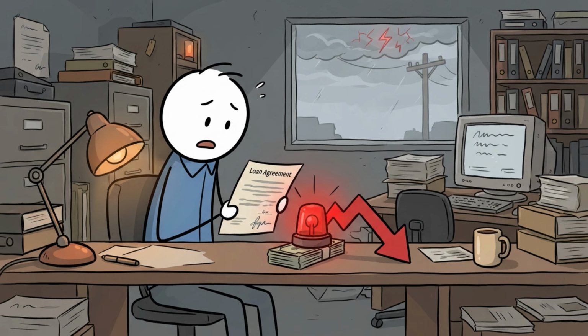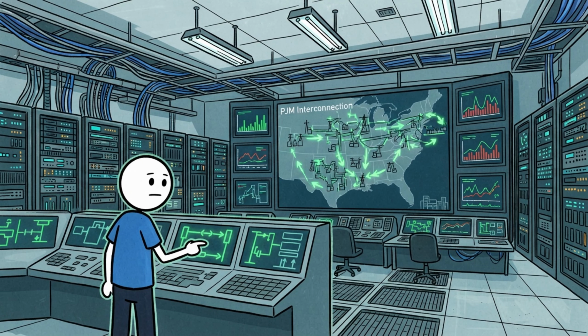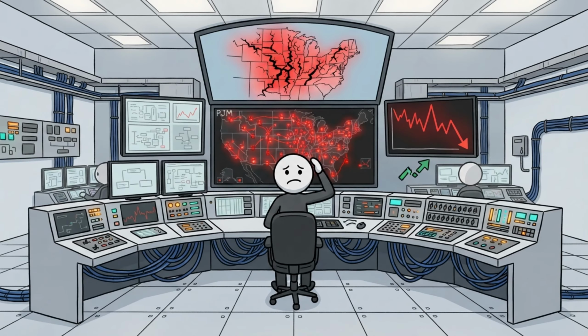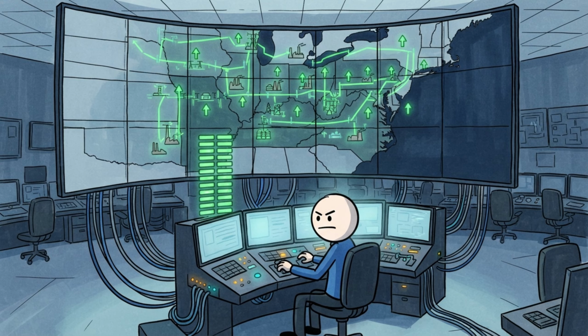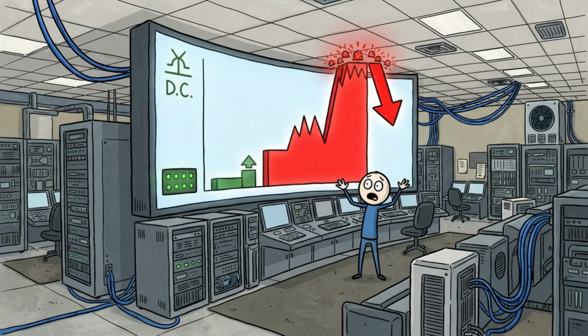But scale makes the grid risk dramatically worse, not better, because larger loads require larger, slower transmission upgrades that a utility can't simply expedite for a fee. Google has reported connection delays of up to 12 years specifically tied to its largest proposed loads. The interconnection queue punishes exactly the scale that makes the rest of the business more efficient to run.